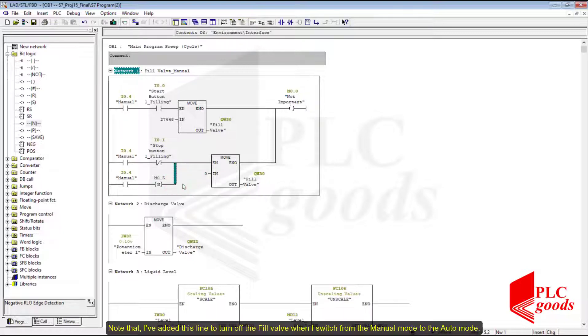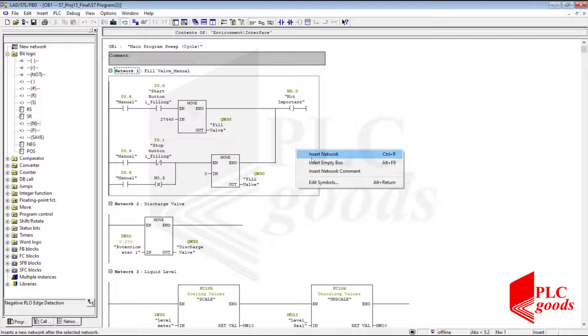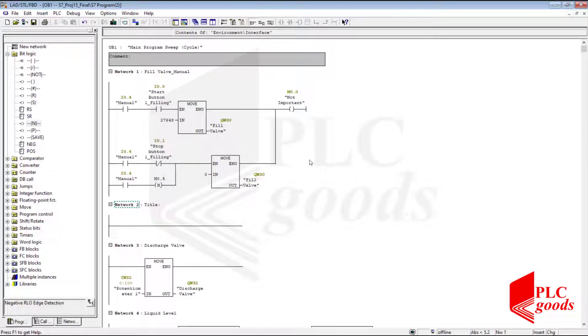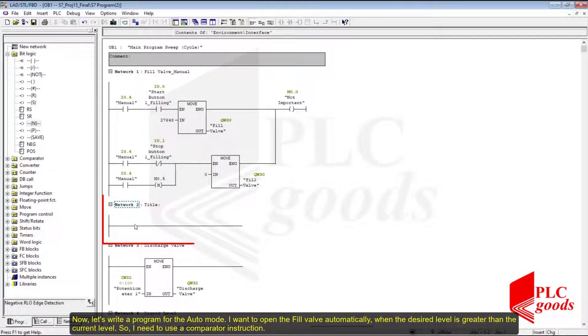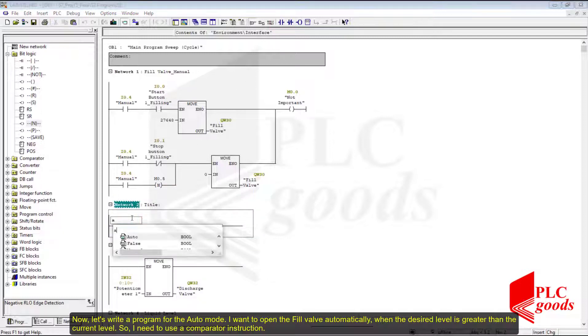Note that I added this instruction to turn off the fill valve when I switch from manual mode to auto mode. Now let's write a program for the auto mode. I want to open the fill valve automatically when the desired level is greater than the current level, so I need to use a comparator instruction.